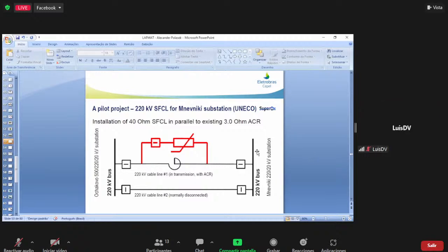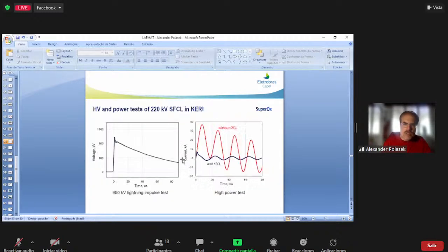Yeah, go ahead. Yes. Here is just to show you how it is installed in parallel. Here you have an air core reactor. That's a conventional fault current limiter. They put the superconductor limiter in parallel with the air core reactor, because if you have a problem with the superconductor, you can use the air core reactor as a fault current limiter. And in some tests, you can see the red curve without the fault current limiter, and the limitation is amazing, the limitation of the fault current using the superconducting fault current limiter.